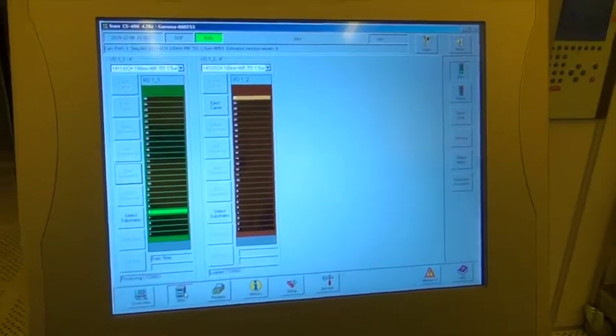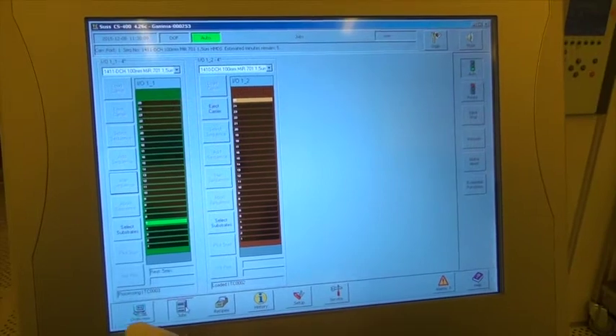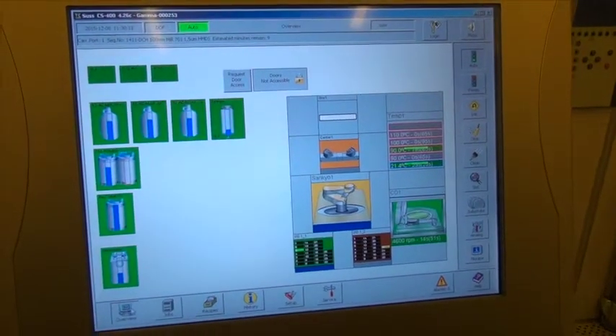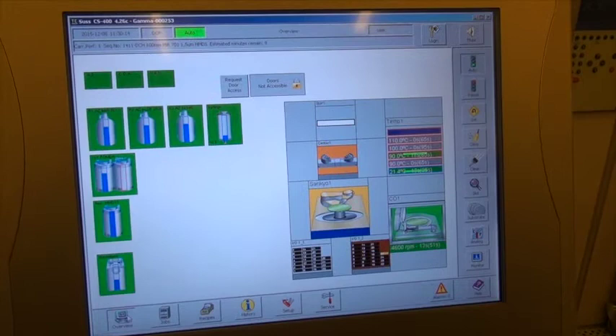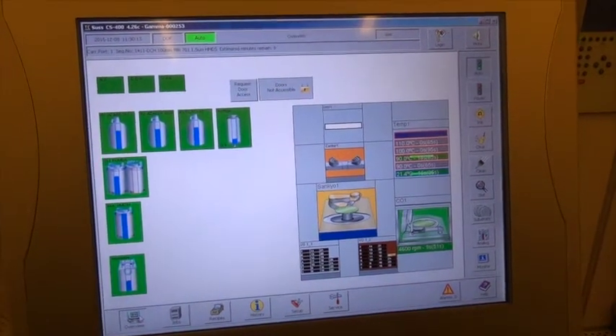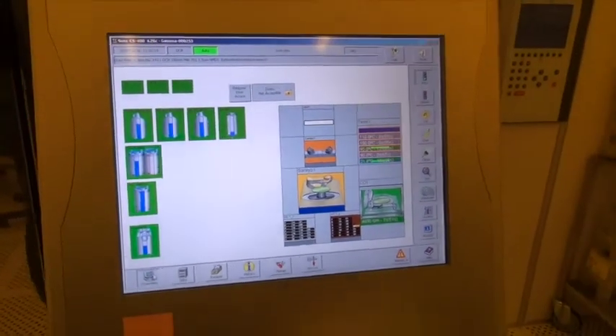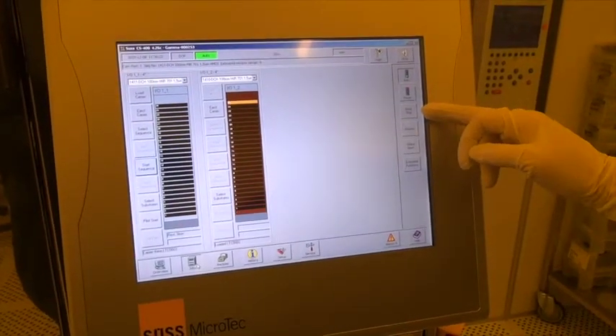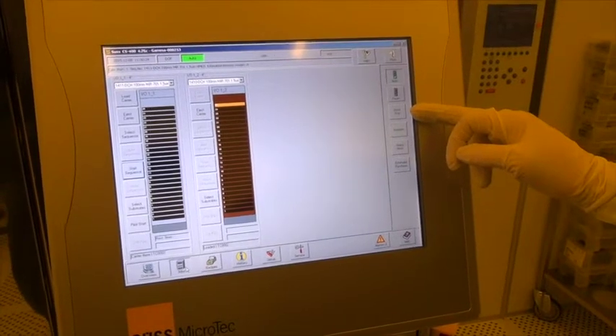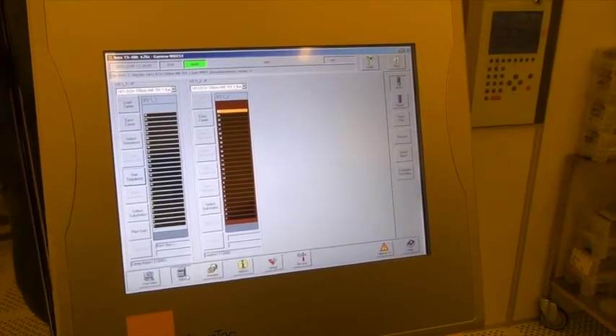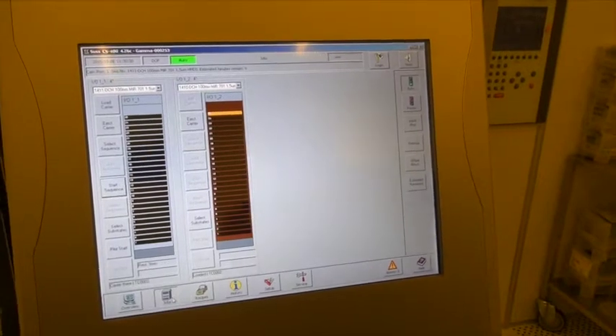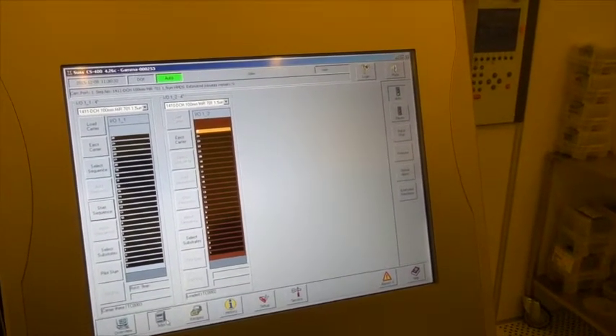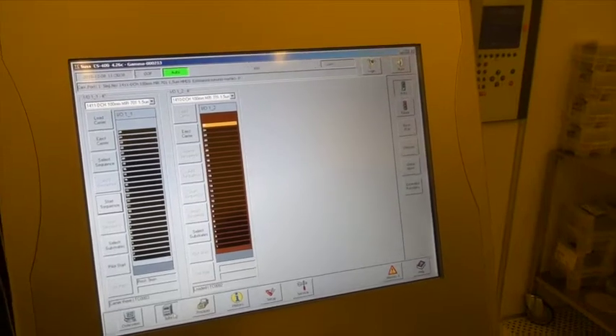While the machine is processing we can follow the wafers around in the machine on the overview page. And should we decide not to process any more wafers out of the ones we've loaded I can press job and select input stop. This means that wafers that have already started processing will be finished but the ones remaining in the input cassette will not.